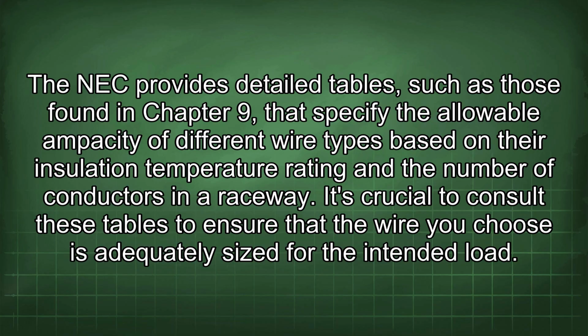The NEC provides detailed tables, such as those found in Chapter 9, that specify the allowable ampacity of different wire types based on their insulation temperature rating and the number of conductors in a raceway. It's crucial to consult these tables to ensure that the wire you choose is adequately sized for the intended load.